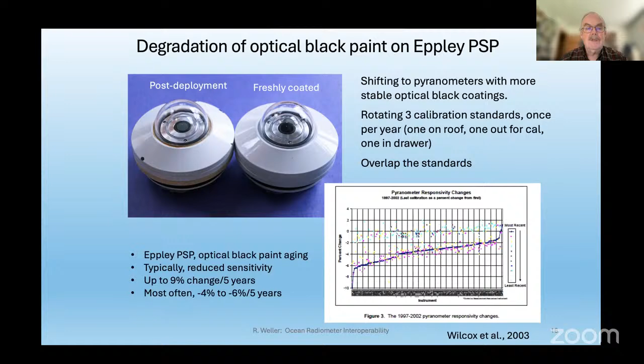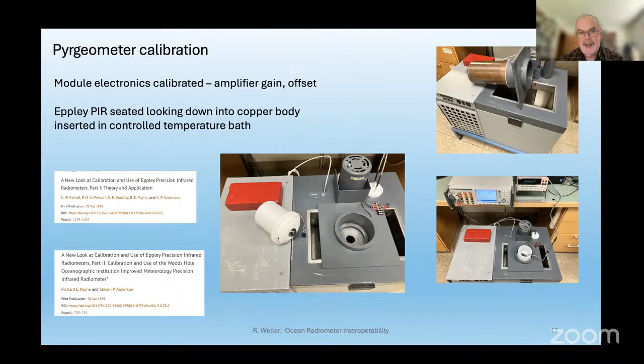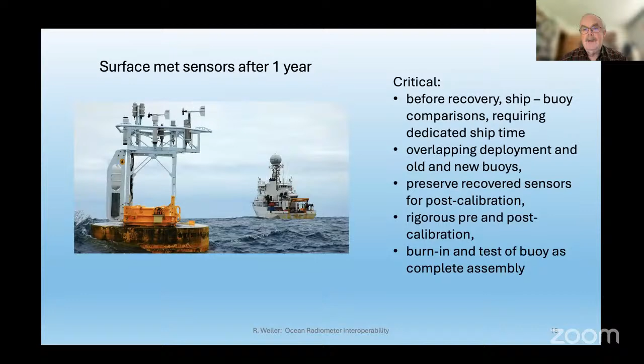How do we calibrate pyrgeometers? Well, we have a stable temperature bath with good standards. We made a copper body and we painted the inside of the copper body with Parsons black. The pyrgeometer module nests inside and looks downward at this stable temperature bath, and that's how we check the calibration on the pyrgeometer. And we do a lot with long-term deployments. I think Danielle's going to talk about intercomparisons too. We do that at sea.